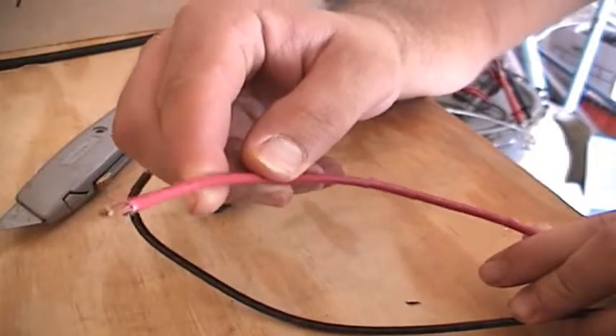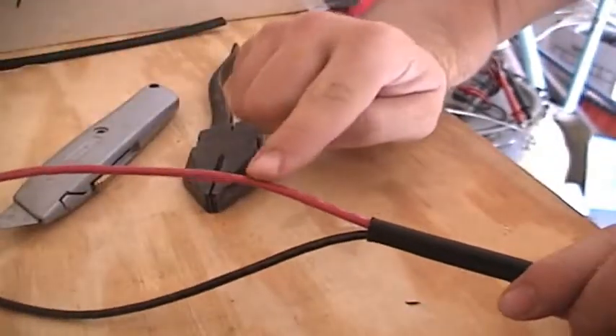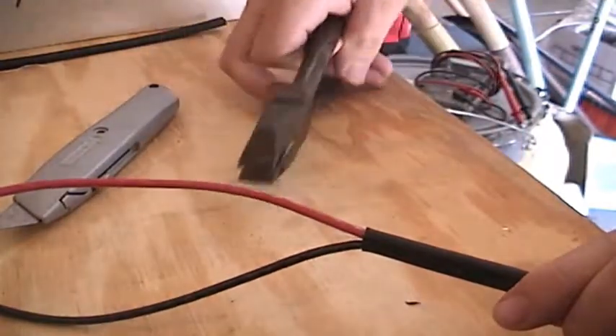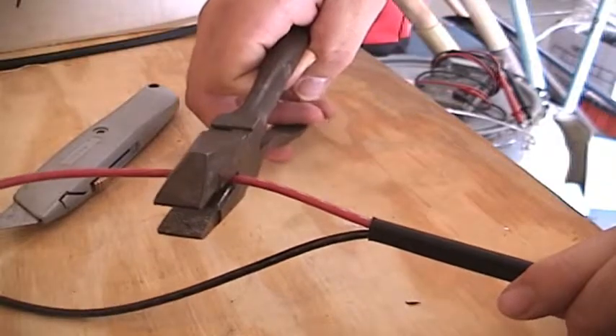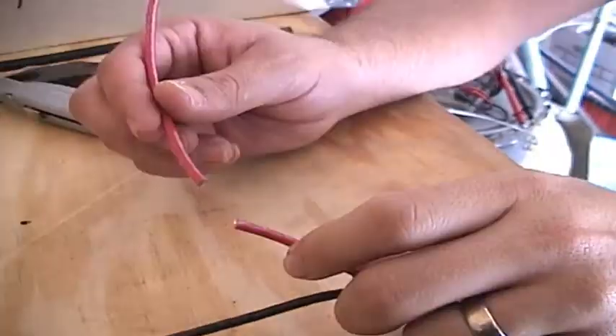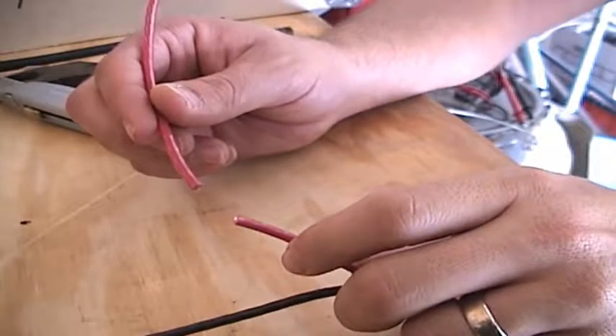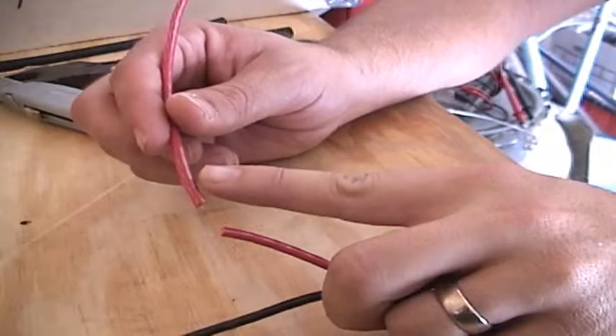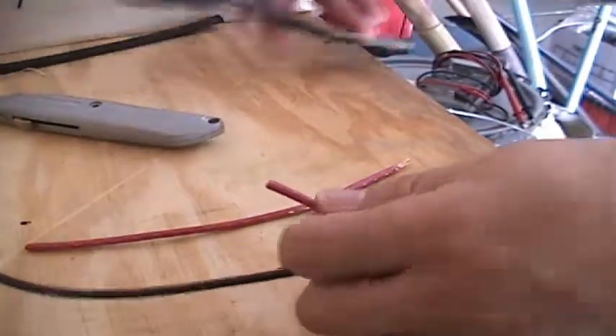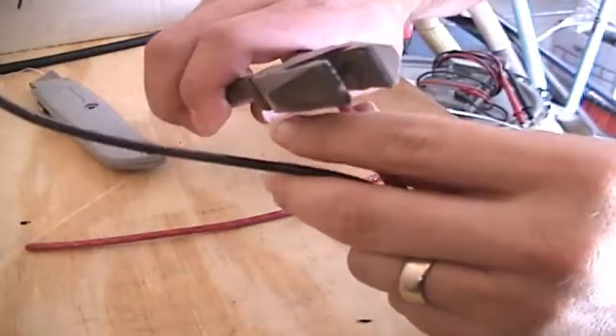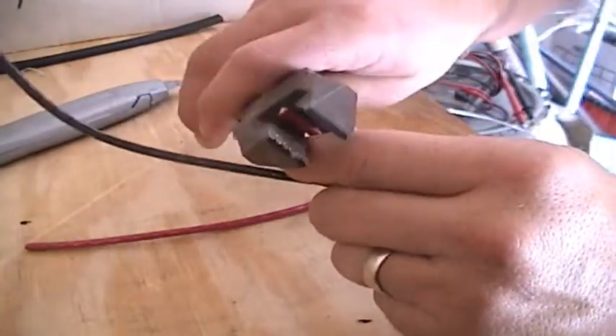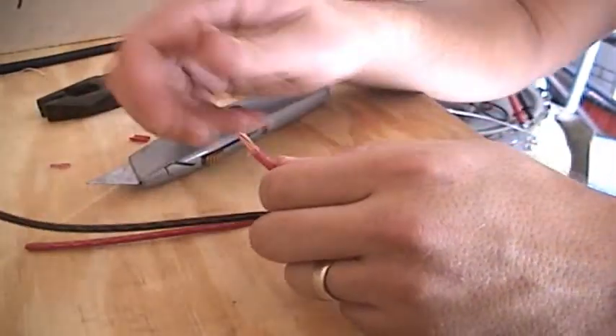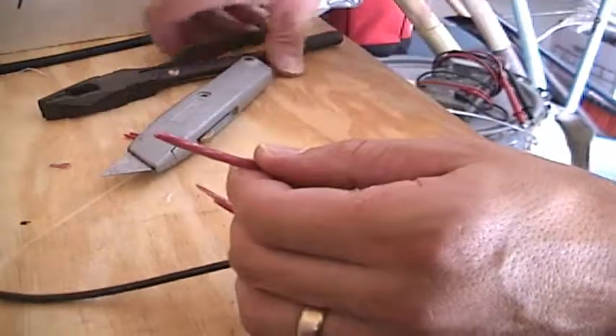Now let's take the red 10 gauge wire and we're going to cut it about 2 inches above the outer skin. Go ahead and get our wire cutters. Now let's remove about 1/2 inch of insulation off of both ends of the red cable that we just cut. Again, we can do this using our wire cutters and our utility knife. And then let's do the next piece.